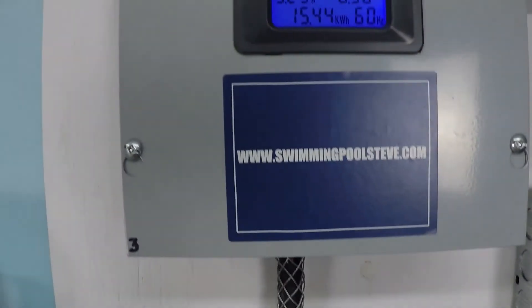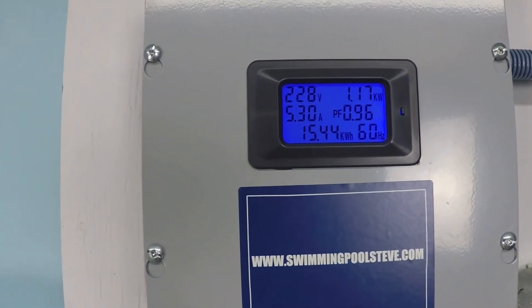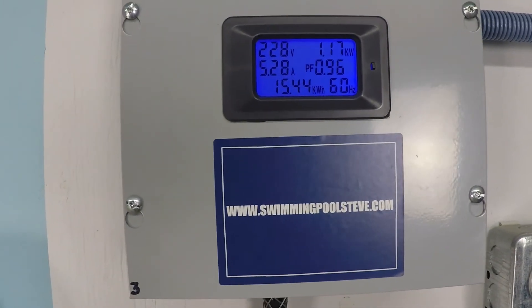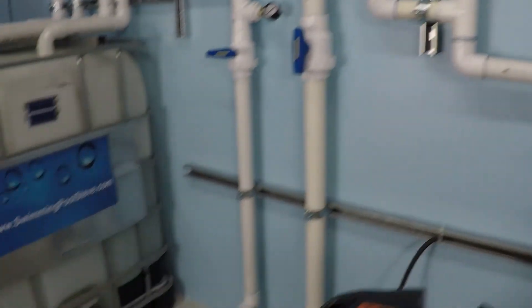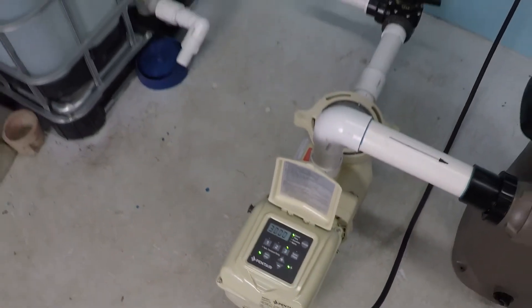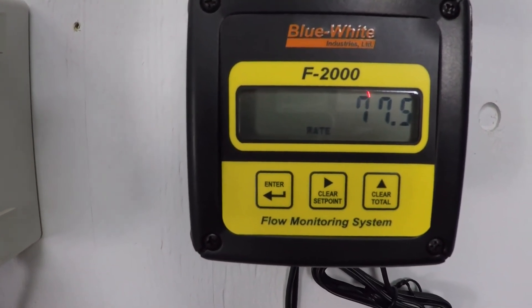About 77.5 gallons per minute, 1.17 kilowatts — that's 1,170 watts. Watch the decimal point move there on the display. 5.28 amps of current draw.